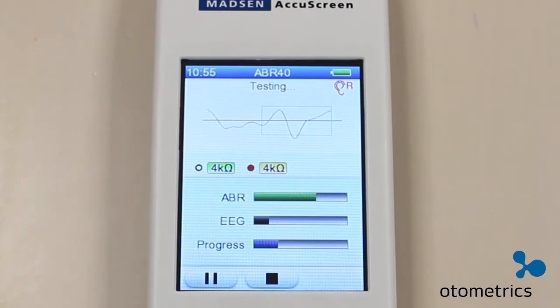On rare occasions, the device determines that a pass will not be possible because the ABR is so weak or the noise level is too high. When this occurs, the Accuscreen will stop the test before the blue bar has reached its endpoint. This is called a fast refer, and may, under poor test conditions, occur quite fast after the test starts.